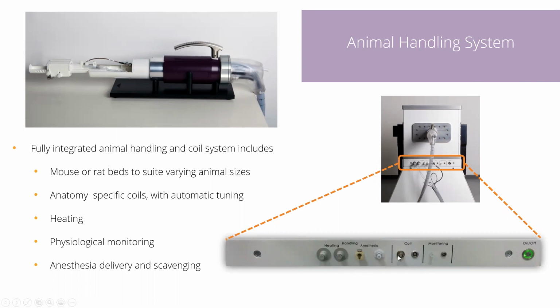There's obviously connections for the coil to the electronics cabinet and physiological monitoring. So typically, I would only use respiratory monitoring, but there is the possibility to monitor additionally both temperature as well as the ECG signal. And that ECG signal can be used to perform ECG-gated imaging, and the respiratory signal can be used to perform respiratory-gated imaging as well.